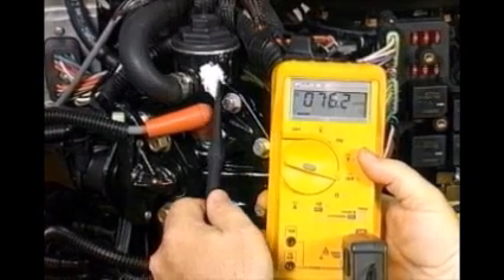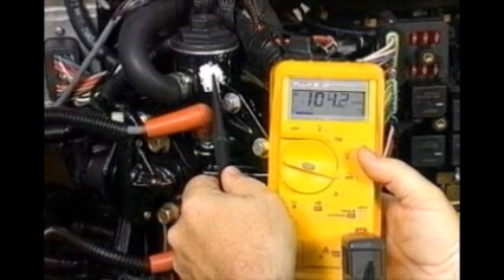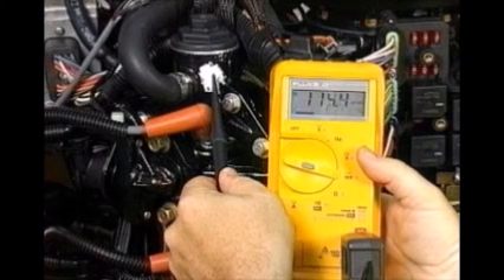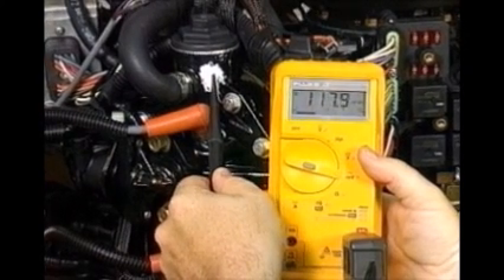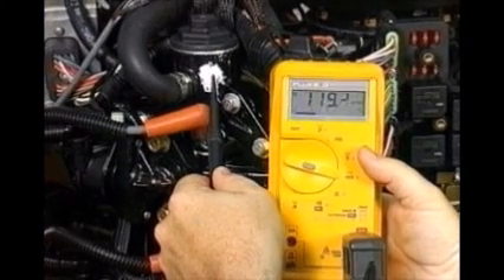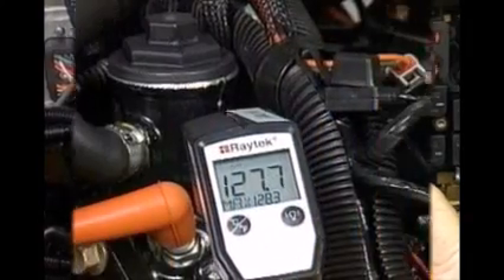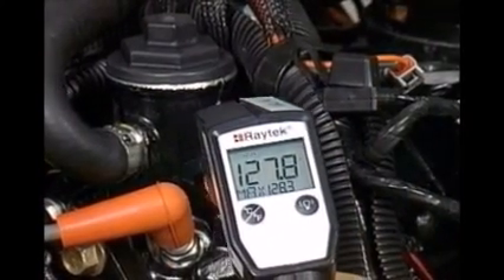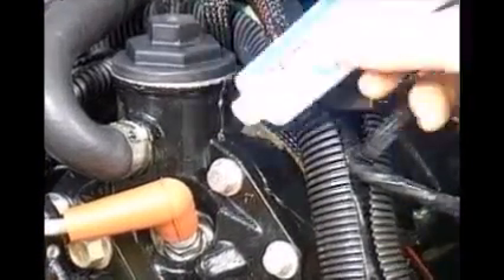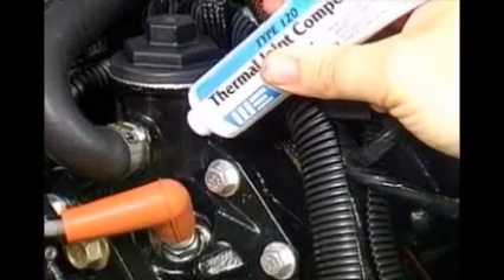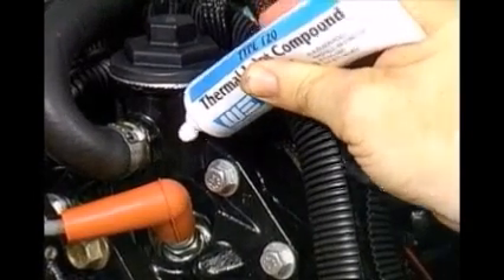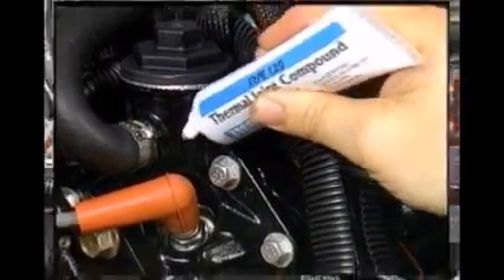The two most common cooling system problems are overheating and overcooling. Pyrometers are used to check power head temperature. Common types include probes and infrared non-contact pyrometers. When measuring power head temperature with a probe, use Wakefield thermal joint compound to ensure an accurate reading.